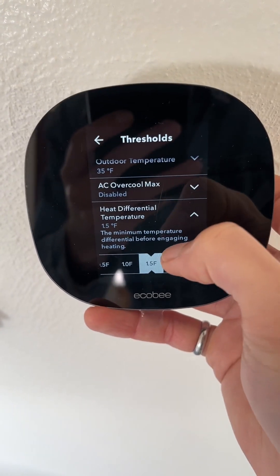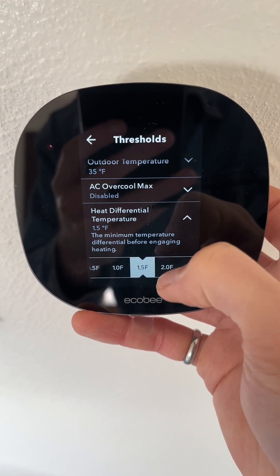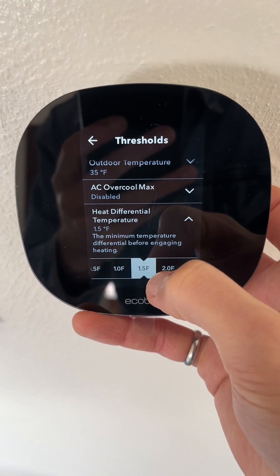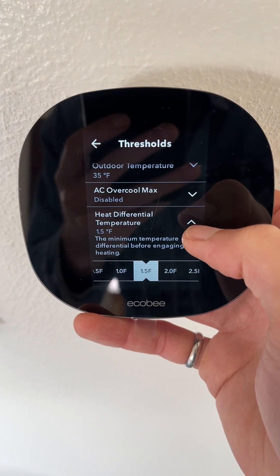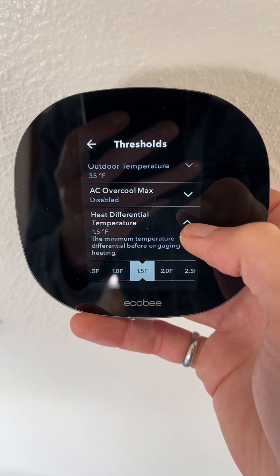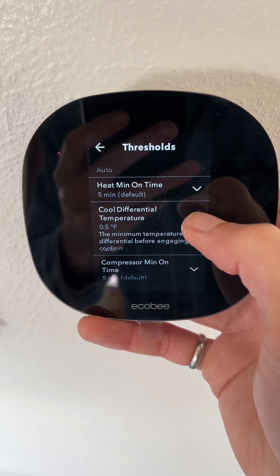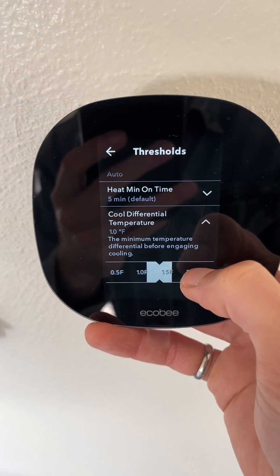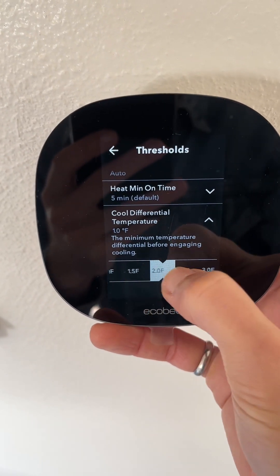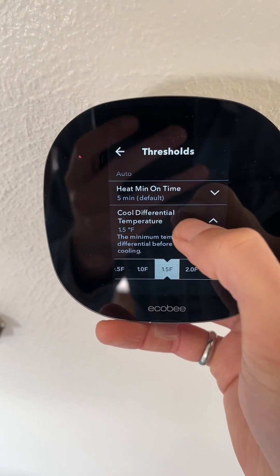This means if I have the thermostat set to 70 degrees, it will get down to 68.5 degrees before it turns the heat on. That is going to be a realistic goal for this home, and it will allow the furnace to cycle much less often. I'm going to do the same thing for cooling and go to one and a half degrees. You could go all the way up to three degrees, but I think that's a little high, so we're going with one and a half.